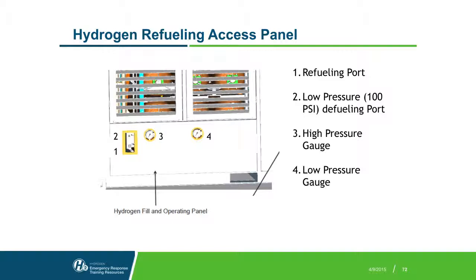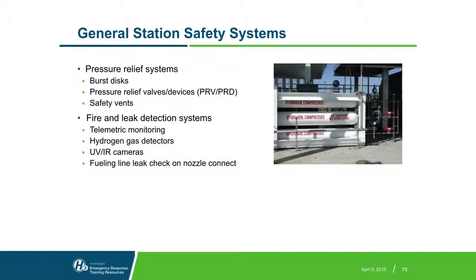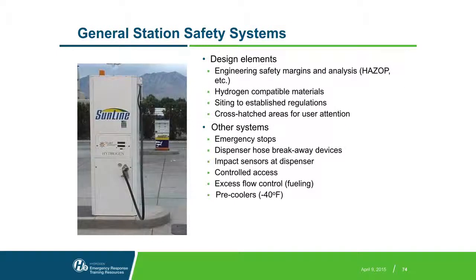pressure gauges. In terms of safety systems at the station, you have high pressure storage, so you'd expect to find pressure relief systems. There's also gas sensors employed and flame detectors at the fueling station. Other design elements that you'd expect to see at other fueling stations, including an e-stop there. There's breakaway devices, impact control, and so forth. They do go through safety analysis, just like this unit did. It went through an FMEA before it was built.